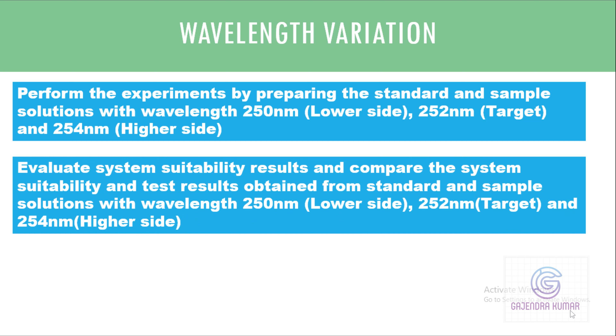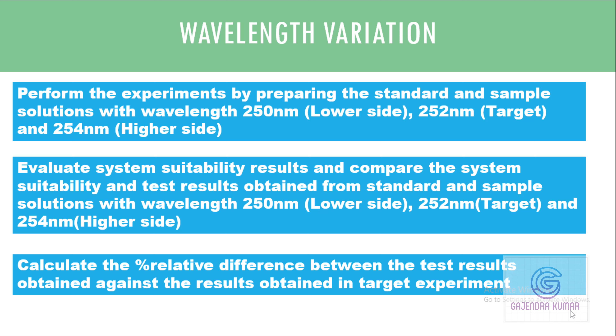So again, you need to evaluate the system suitability results and calculate the percentage relative difference of test results against the target conditions. Here the target condition is the 252 nanometer. So how to do it? See this example. This is a set of results where all the results are meeting the acceptance criteria. Here the percentage relative difference is also meeting the acceptance criteria. Let's see another side also.